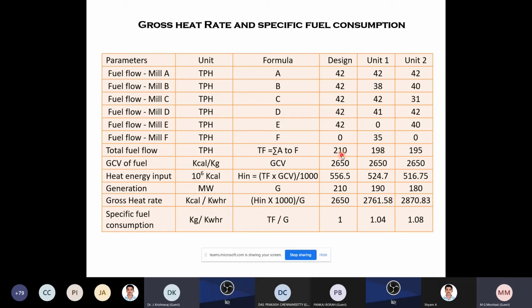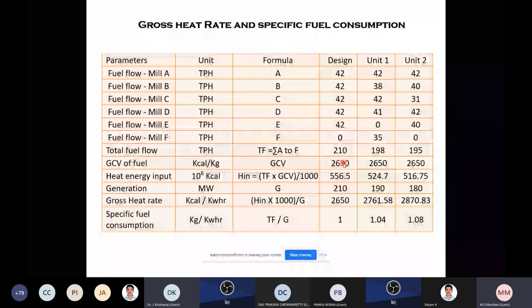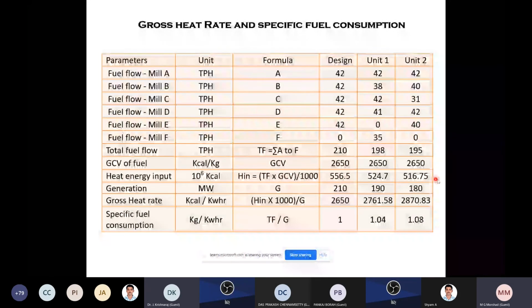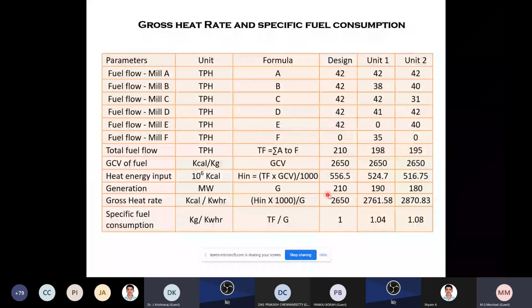You see, there is a design value 210, here I am getting 198. GCV of the fuel is the same. So you multiply this one to get the total energy input and total heat generation. So total gross heat rate you can calculate accordingly, and specific fuel consumption you can calculate accordingly. Gross heat rate 2650 is the design. Now in unit 1 it is 2761 gross heat rate, specific fuel consumption 1.04, and here it is 2870, 1.08. So you can establish the gross heat rate and the specific fuel consumption in any power plant. Okay, is it clear? Yes, sir. Okay, good, very good.